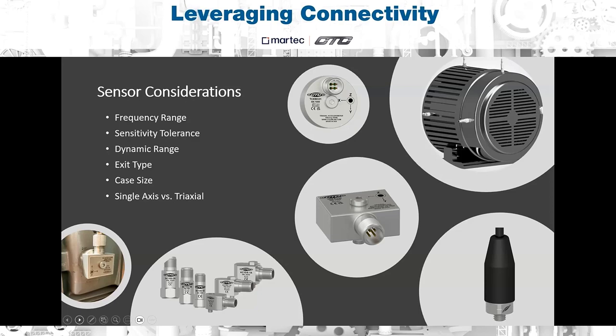For example, a general purpose sensor with a sensitivity of 100 millivolt per G will be able to accurately measure frequencies between the range of about half a hertz all the way up to 15 kilohertz. However, if you would like to use a low frequency sensor, that type of sensor will have a 500 millivolt per G sensitivity and will be able to accurately measure frequencies all the way as low as 0.1 hertz. So for low speed applications, this would be a better option than a general purpose. For this reason, knowing the run speed of your equipment is extremely important when choosing the correct sensor, as the frequency response should match.